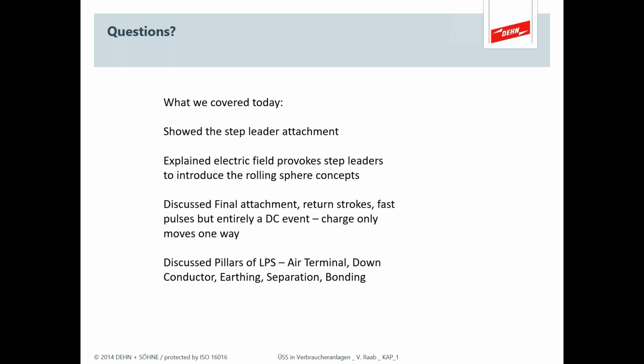Well, it's back to the risk evaluation. The risk evaluation guides you to select the minimum protection factor from the list of options 1, 2, 3, 4. So if your risk is really high, say a hospital full of babies and oxygen tanks, then your protection methods are suggested to be more stringent to reduce your risk to an acceptable threshold. And if you've done that, it tells you what category, what class of protection. Then you apply that to the calculation, and your heights and your distances all factor in. So by factoring in your risk, it becomes a factor in your future calculations. I think that gets you most of the way to the answer. Yes.